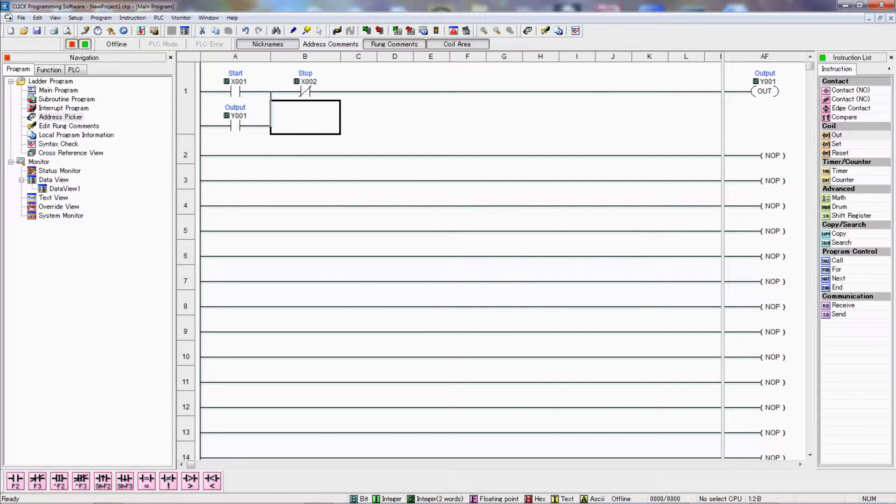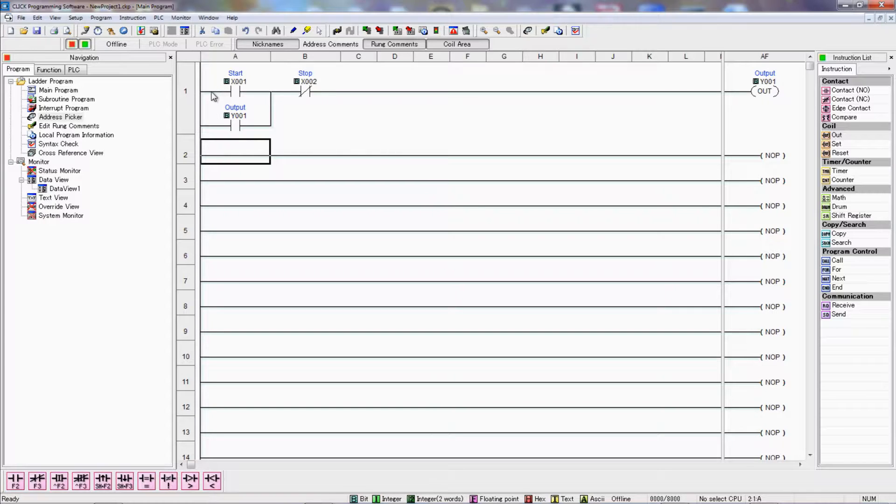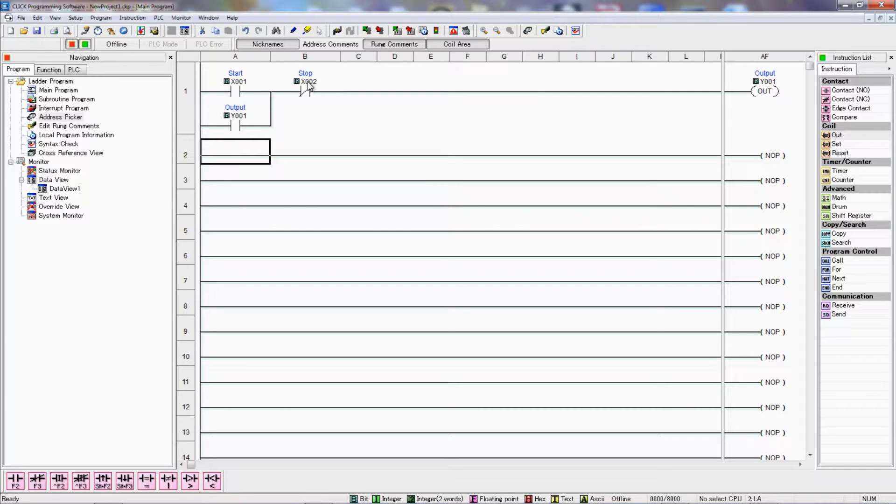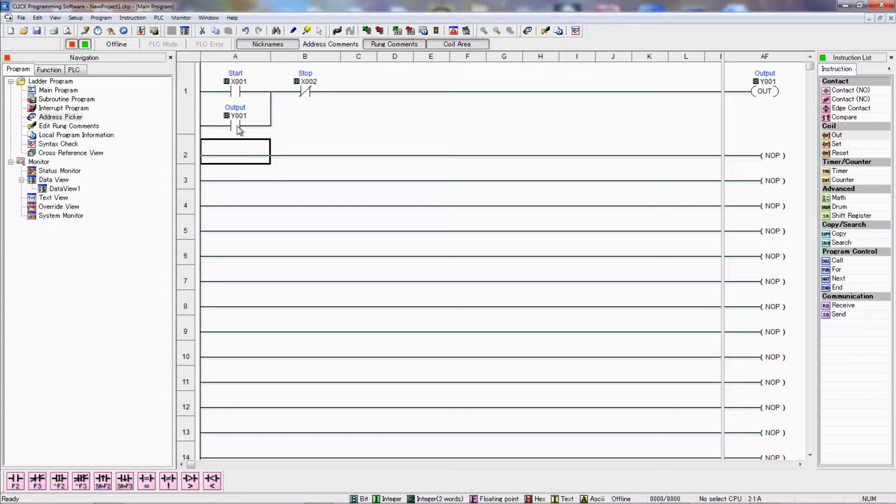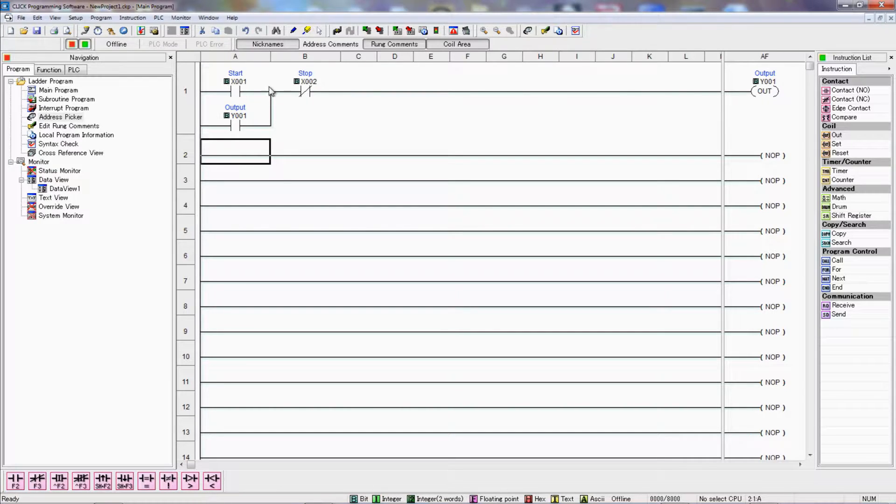So the way this works is when you press the start button, the way to look at this when it's branched like that is this is an OR statement. If you're going to think of this as conditional logic, when the start button is pushed, or this output is on, and this output is not on, activate this output. So when we begin the ladder logic, the start button is open, we depress it, the stop button is also open, but the normally closed contact makes it act as though it's closed. So the contact is allowed through to the output, and Y001 turns on. This causes this to become true, latching itself on.